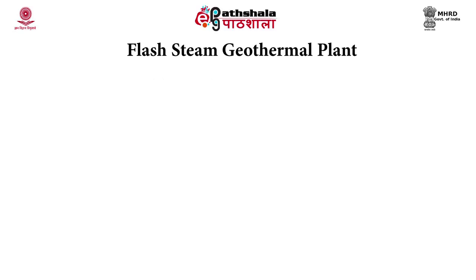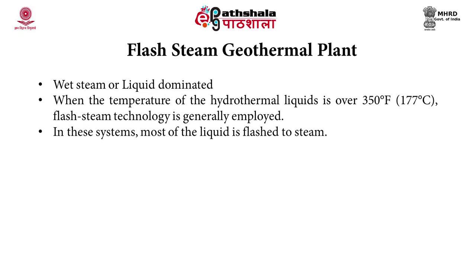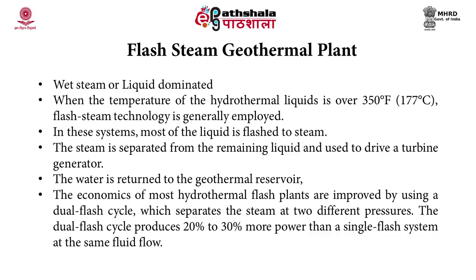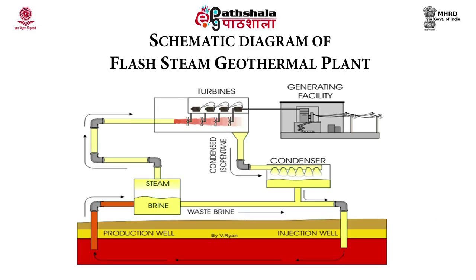The second type is the flash steam geothermal plant, also known as a wet steam or liquid dominated plant. When the temperature of hydrothermal liquids is over 177 degrees Celsius, flash steam technology is generally employed. This is the most common type of geothermal plant. Most of the liquid is flashed to steam; the steam is separated from the remaining liquid and used to drive a turbine generator, while the water is returned to the geothermal reservoir via an injection well.